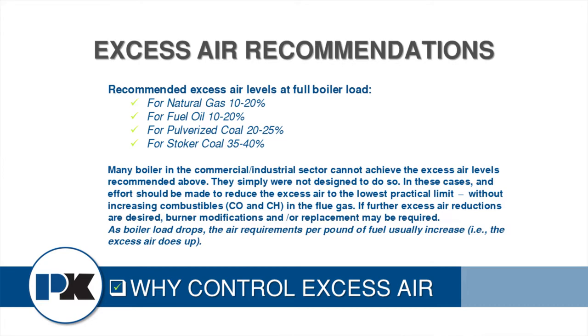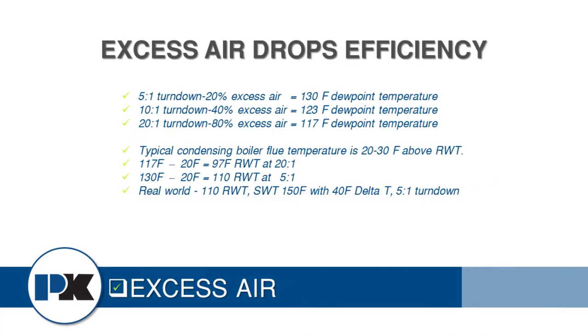Natural gas requires 10.1 cubic feet of air for every cubic foot of gas that you burn — that would be stoichiometric combustion, which can't happen in the field. So we introduce a little bit of excess air to make sure that air gets around every molecule of gas, because once we light the gas the air has to be used in the combustion process.